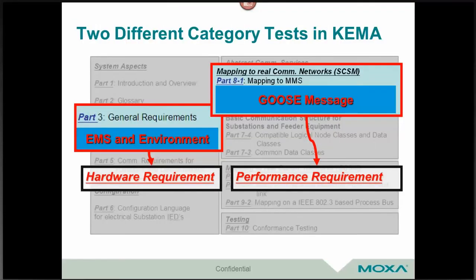So back to KEMA real quick. Not only does KEMA do environmentals, they also test the actual data communication. So they use GOOSE messages, a very critical part of communication within a 61850 type of environment. Basically, it's a message that gives status to a safety relay and from the devices it's talking to, from the other IEDs. Well, this GOOSE message, or Generic Object Oriented Substation Event message, has to be done without ever dropping a packet. It has to be guaranteed it's going to be delivered and has to take priority over all other communications. So KEMA does test for this, and when they did, it was very, very good to see a pass on that. There are some manufacturers that weren't very efficient at doing this, and that led them into some trouble.